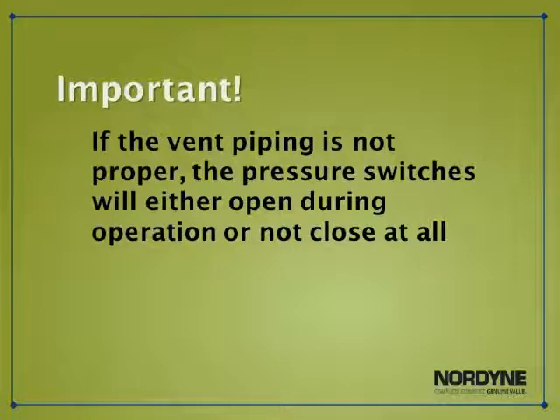If the PVC piping is too small, or the linear length is too long, or there are too many elbows in the vent piping system, this will cause your pressure switches to either open during operation or not close at all. When you're sizing your PVC piping and you're considering using 2-inch, keep in mind your total length of pipe plus all of your elbows. If this adds up so that you're getting close to the maximum allowable length listed in the vent tables, then I would suggest that you not use 2-inch and just go ahead and upsize to 3-inch. This will help you to eliminate problems down the road relating to pressure switch issues.